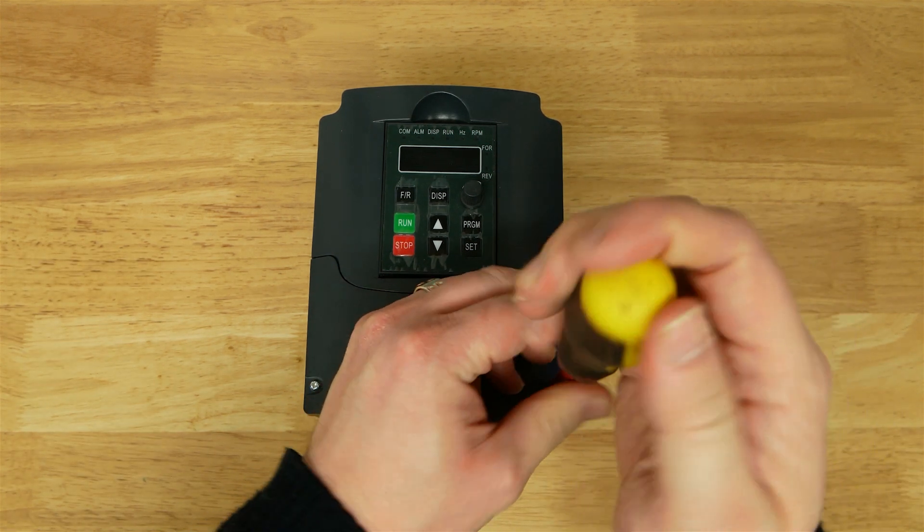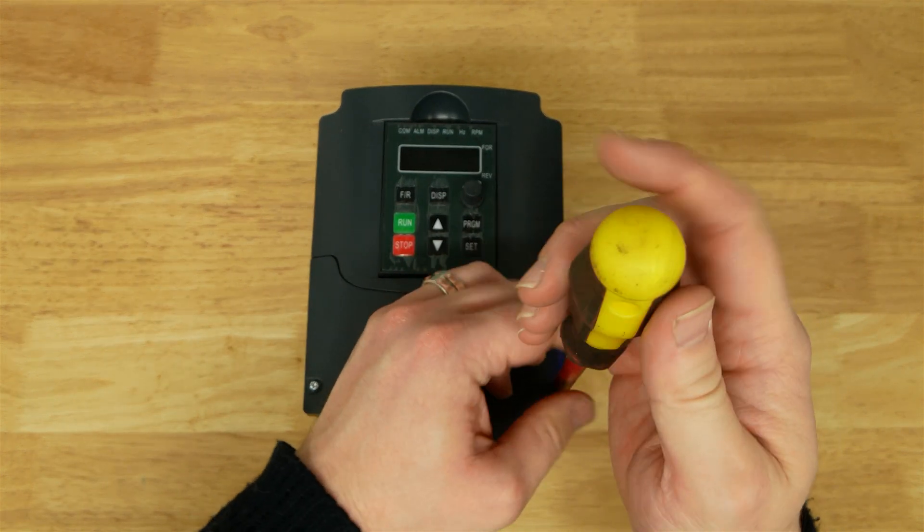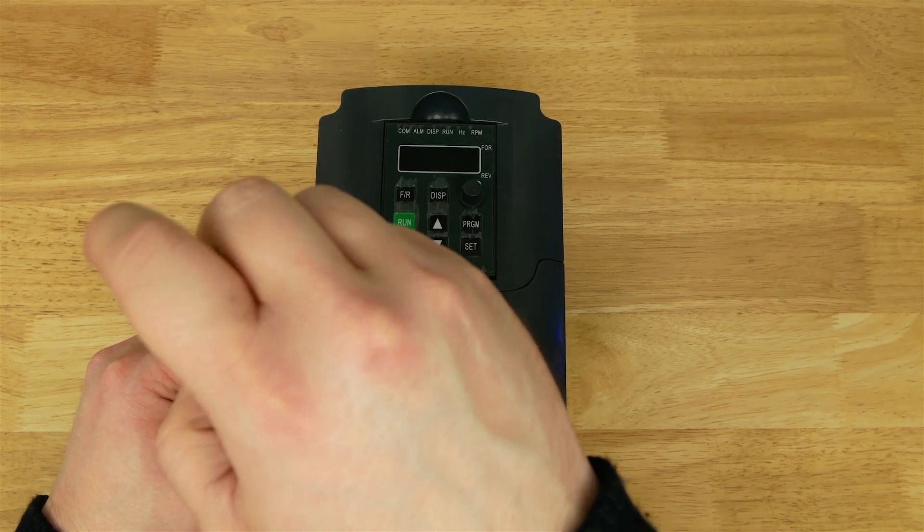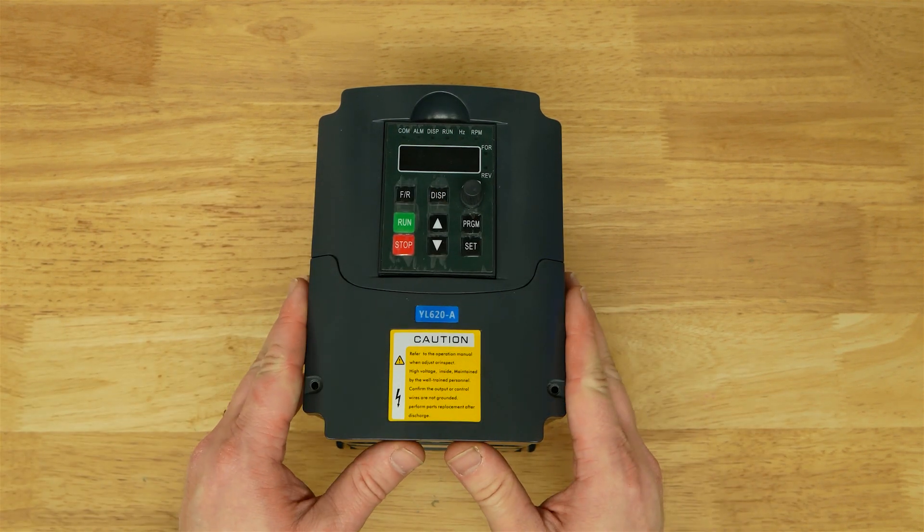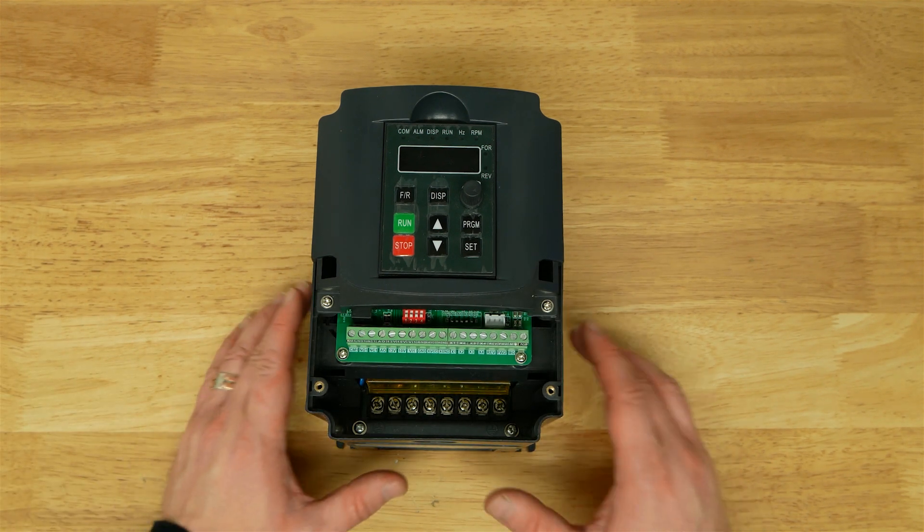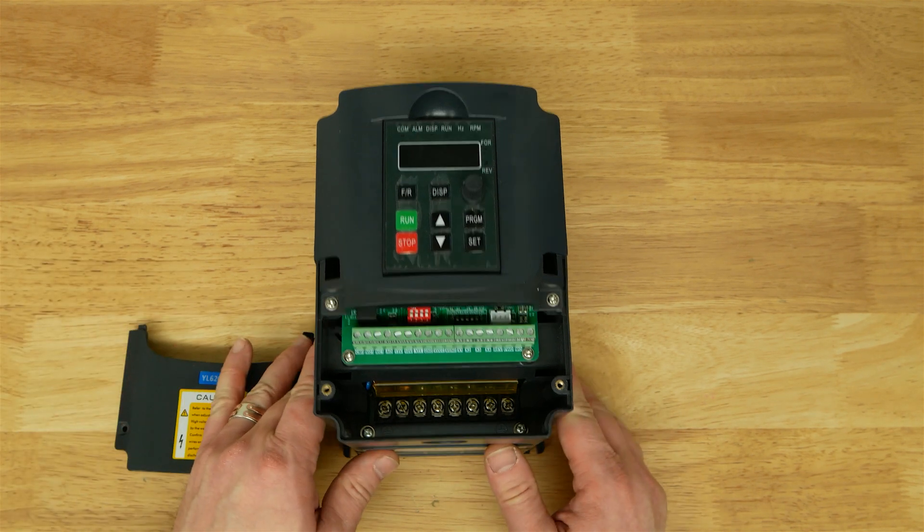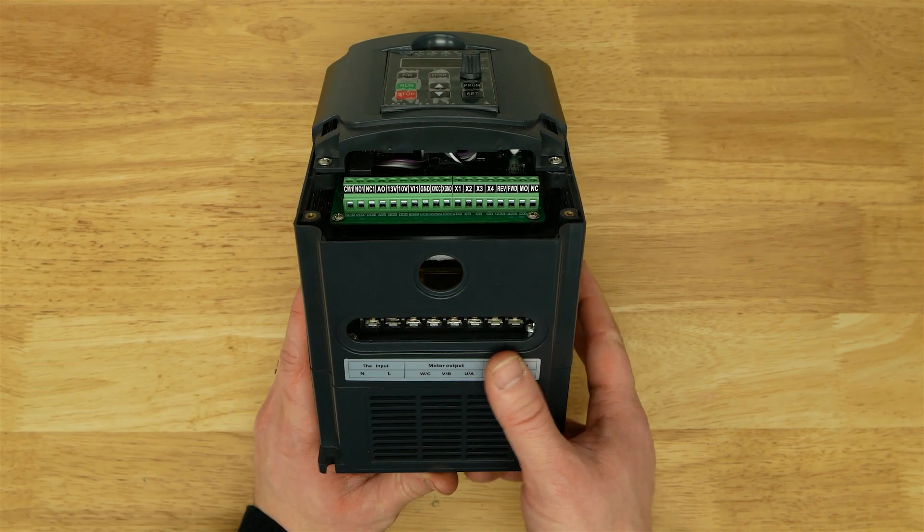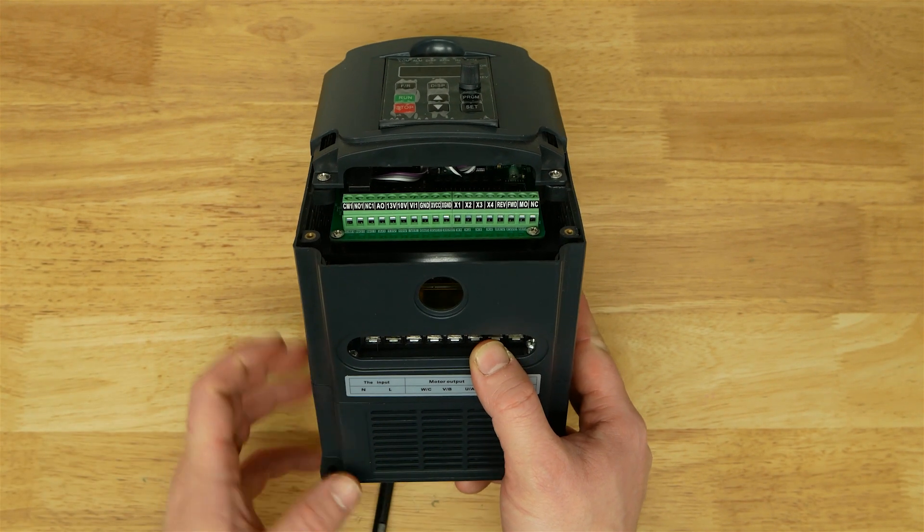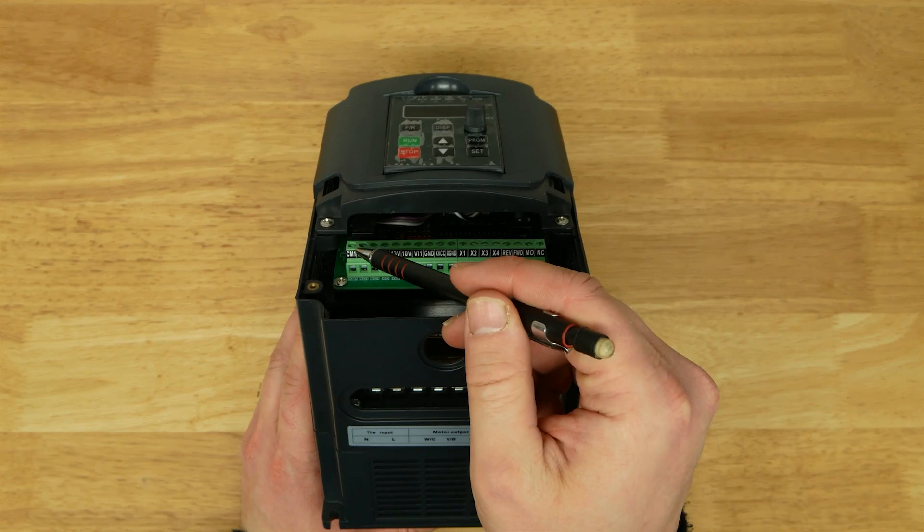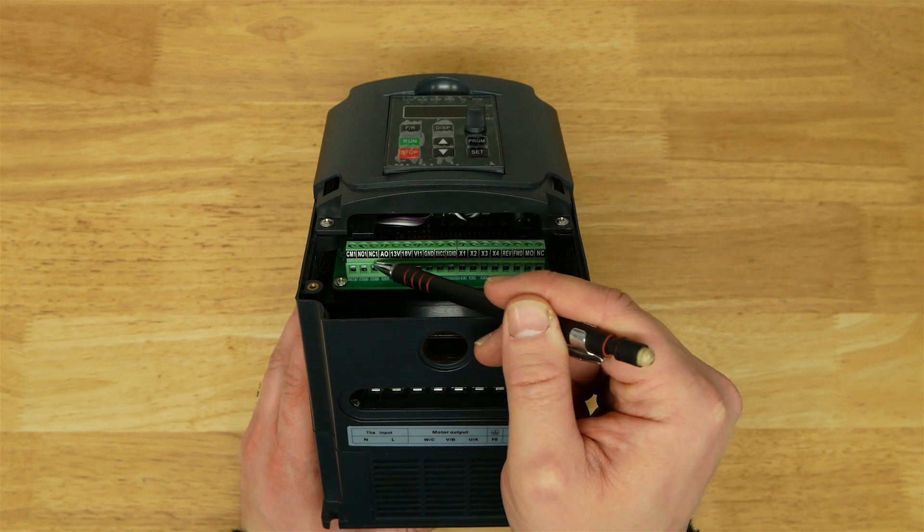We're not doing that this time. We're just going to have the VFD sticking up front of the enclosure. So we pop the front cover off - you need to do this for the installation. You're not taking the whole thing apart, though you can. It's all just screws. There's no odd fasteners to stop you from taking it apart. These are our control terminals. On this side, we have these three terminals here - common, normally open, normally closed. This is a relay.